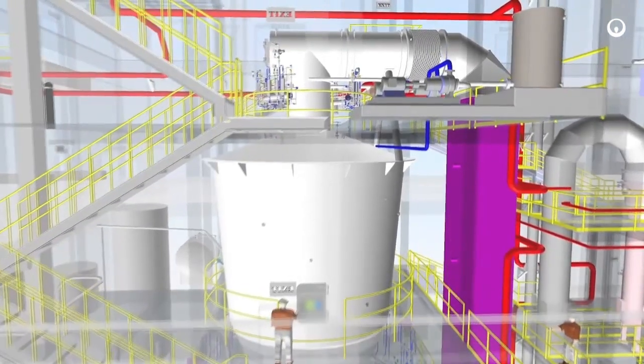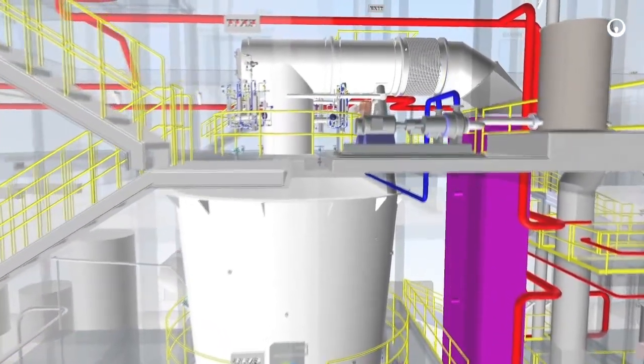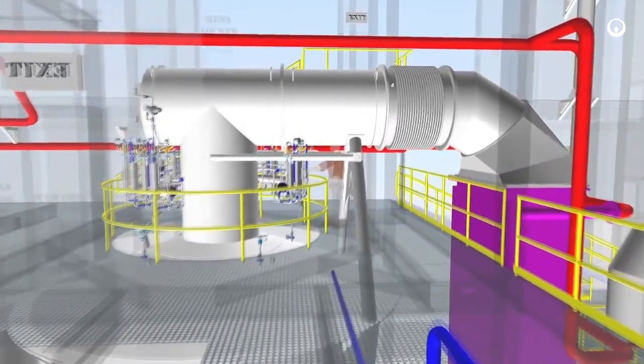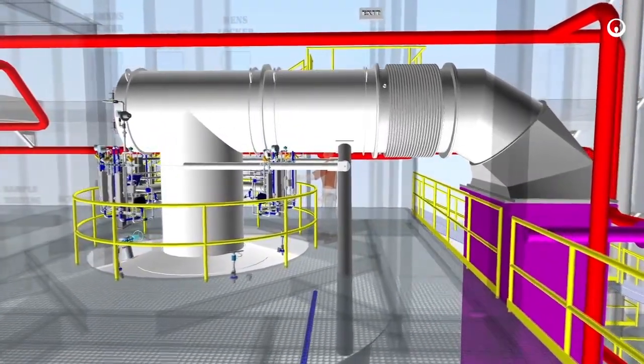Flue gas exiting the reactor is treated at the first stage of air pollution control with ammonia injection through a selective non-catalytic reduction type process to reduce nitrogen oxides.